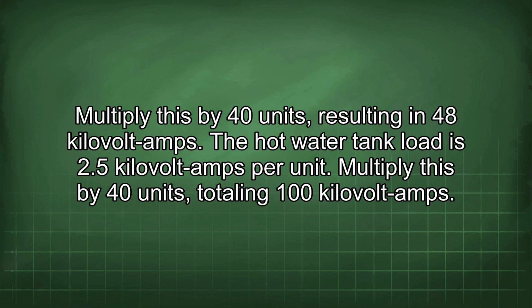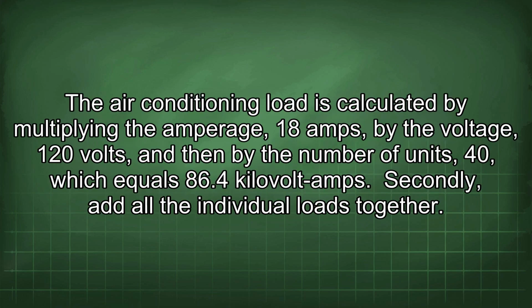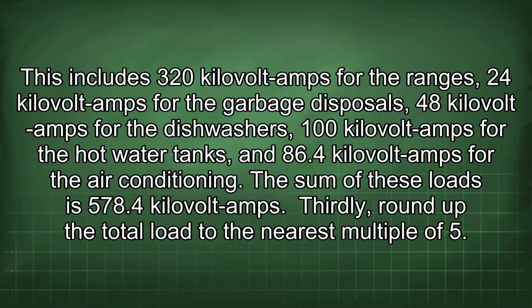The hot water tank load is 2.5 kVA per unit. Multiply this by 40 units, totaling 100 kVA. The air conditioning load is calculated by multiplying the amperage, 18 amps, by the voltage, 120 volts, and then by the number of units, 40, which equals 86.4 kVA. Secondly, add all the individual loads together. This includes 320 kVA for the ranges, 24 kVA for the garbage disposals, 48 kVA for the dishwashers, 100 kVA for the hot water tanks, and 86.4 kVA for the air conditioning. The sum of these loads is 578.4 kVA.